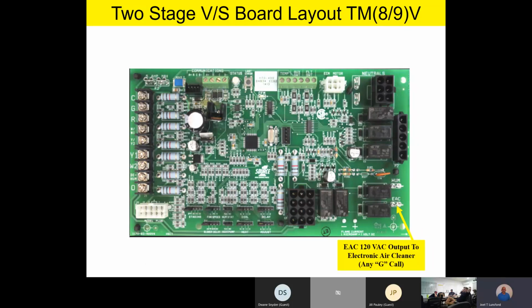Same way with the electronic air cleaner. You'll notice right beside the electronic air cleaner, there's a little relay right here, and that's an isolation relay, so that electronic air cleaner will have 120 volt output to it anytime you have a G call or the fan is running. So if the fan's running, you're going to automatically have an output on there for an electronic air cleaner if you so desire to use that.